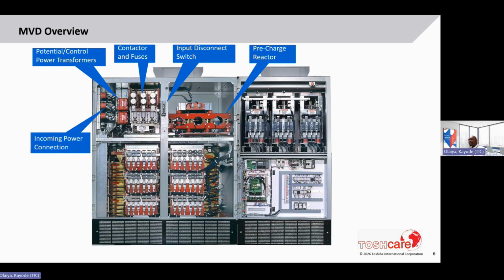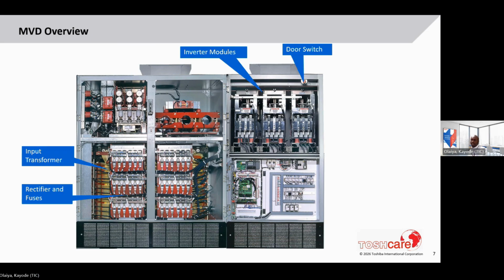Showing you a single line diagram, and then here are pictures showing these same components. This is a frame one drive represented here, and you can see the input power connections. That's where the lightning arresters are in this drive. The PTs I mentioned, those red boxes, the contactors and fuses, then the isolation switch, as well as that subcharge reactor, which we also call the pre-charge reactor. The input transformer is that multi-pulse transformer connected to the rectifiers and fuses in front of it. And then the inverter section, which consists of those three power modules.